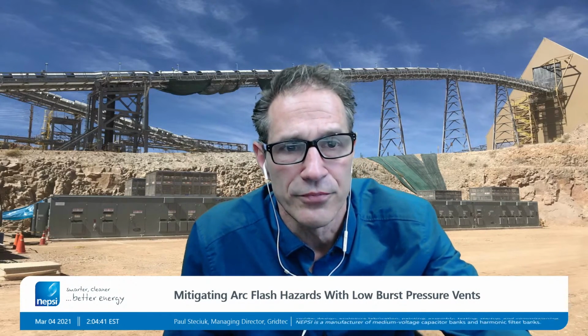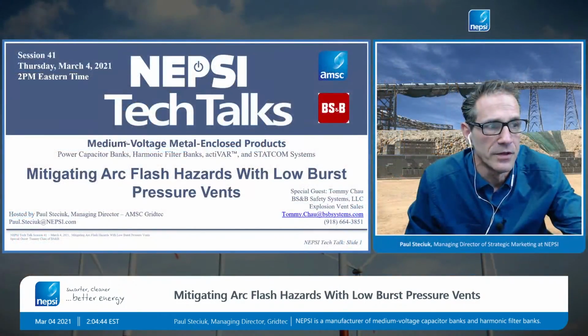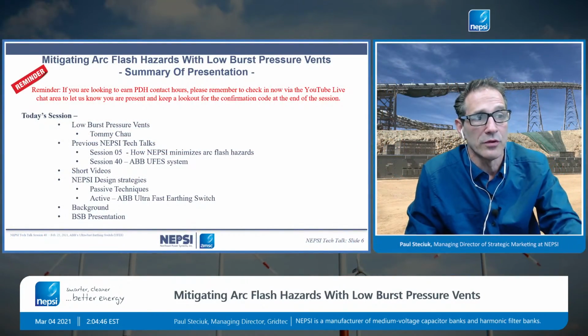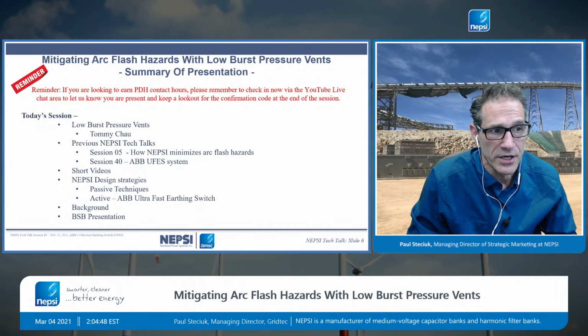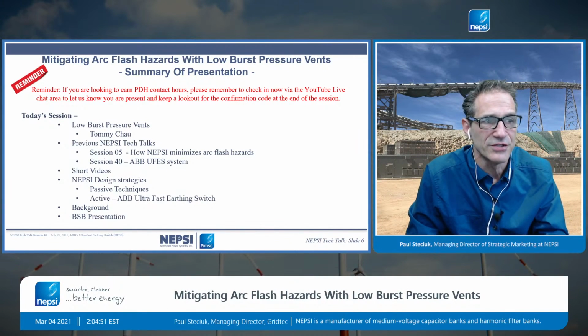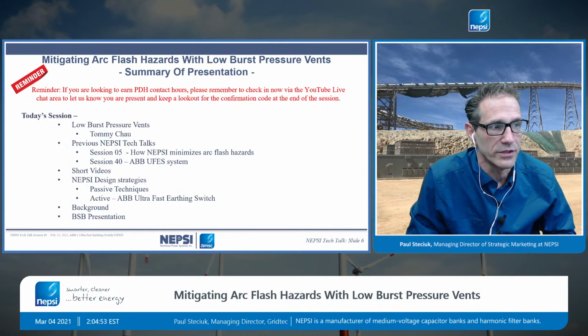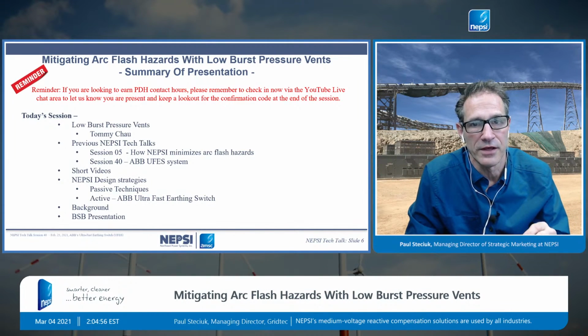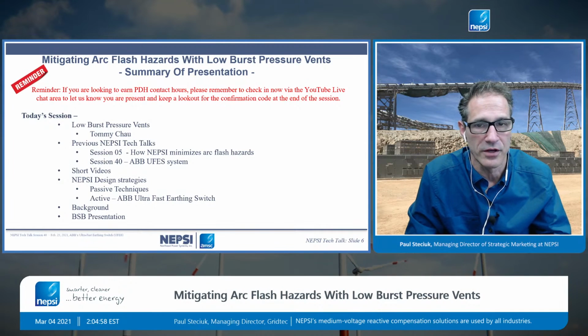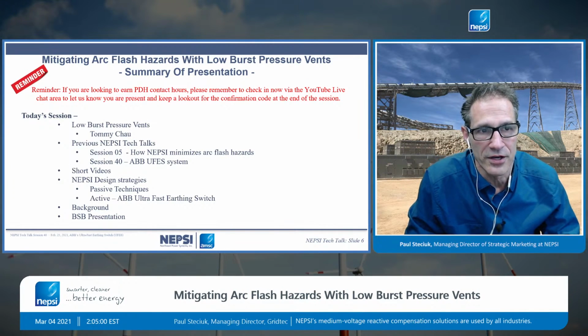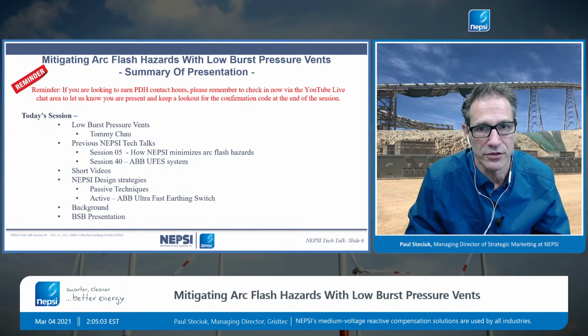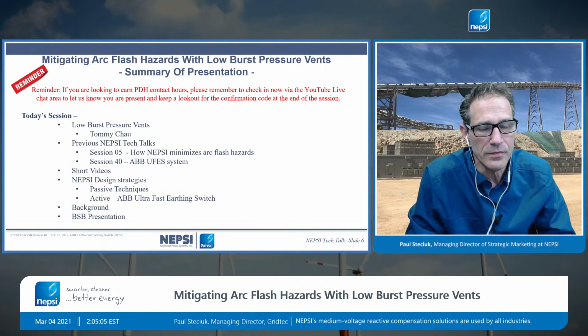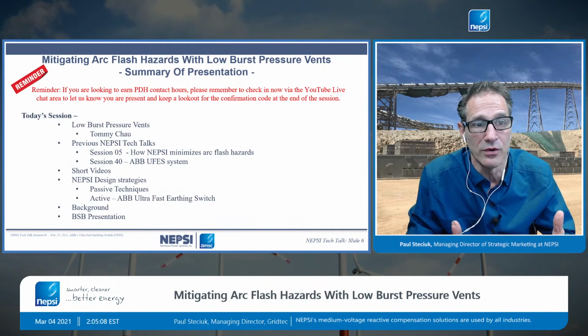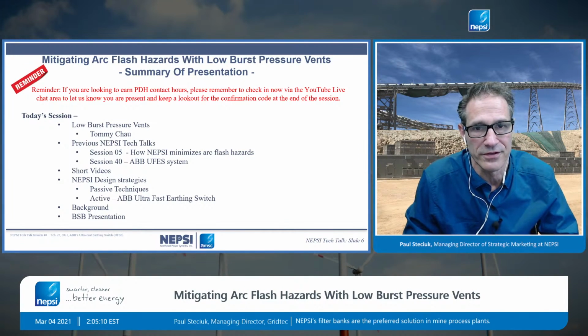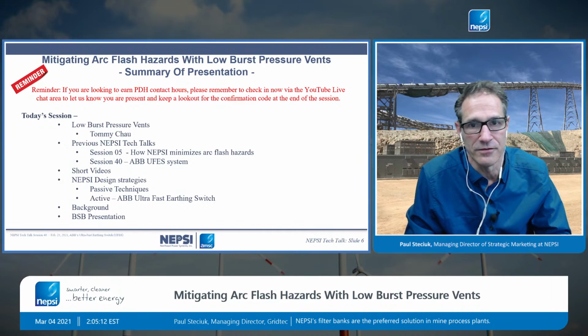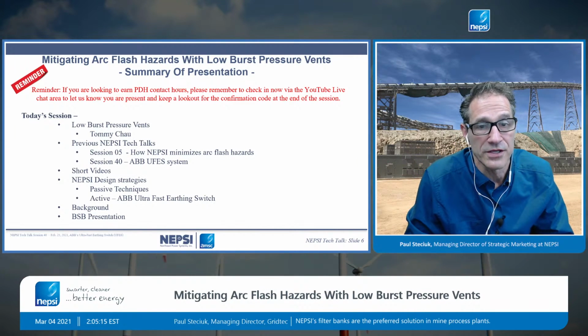So I'm going to flip over to the presentation for a moment and go through a couple details. Today we're going to be doing low burst pressure vents with Tommy Chau. Remember Tech Talk Session 5, we talked about minimizing arc flash events within metal enclosed capacitor banks, harmonic filter banks. There's a list of 30 items to think about when you want to reduce arc flash hazards with metal enclosed cap banks. One of the key ones is let's not have the event in the first place. Let's design equipment that doesn't fail. And that's what our session 5 was about.